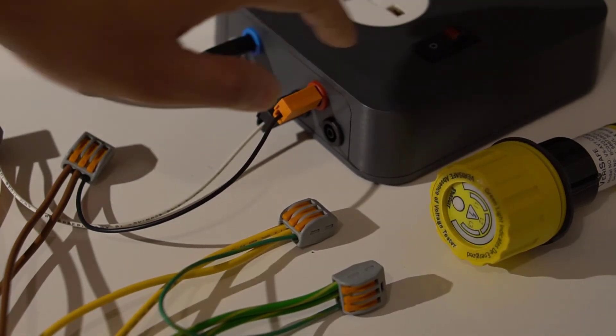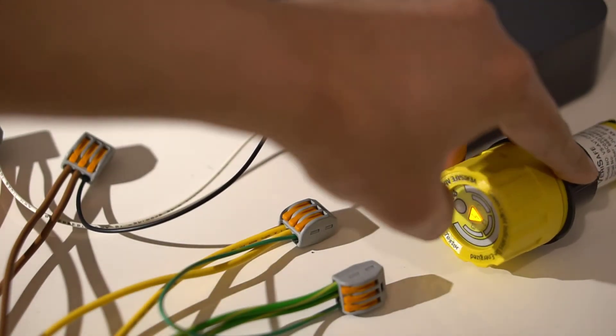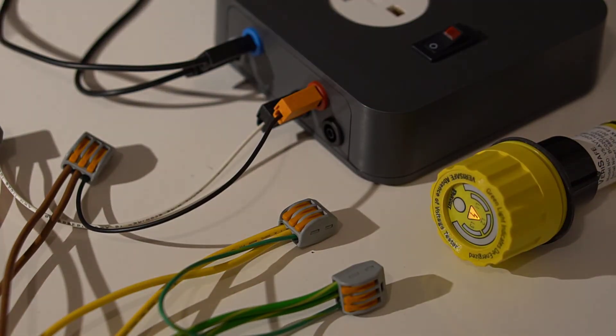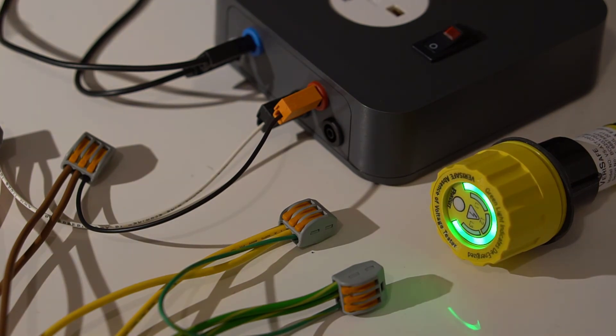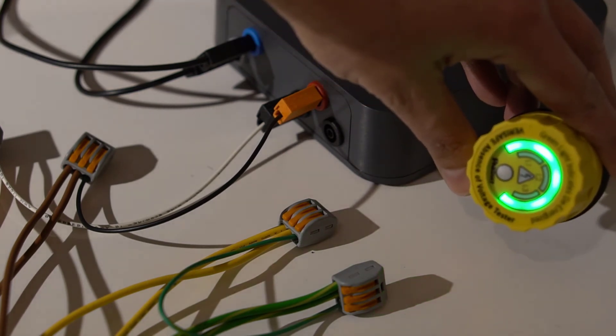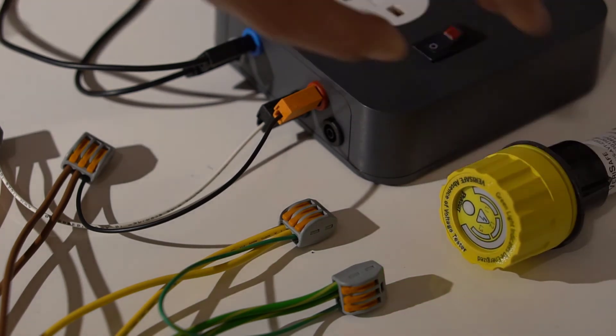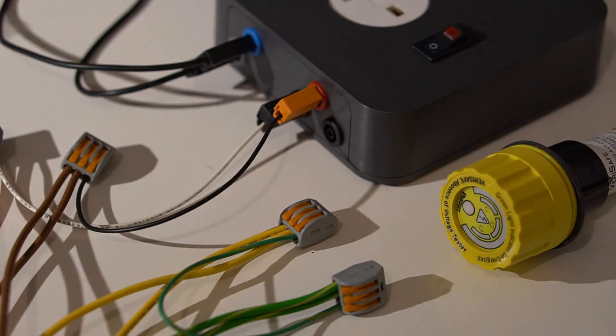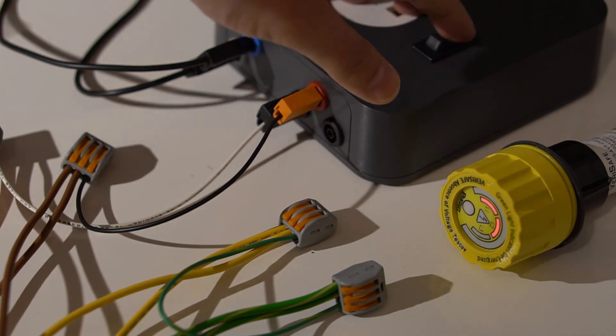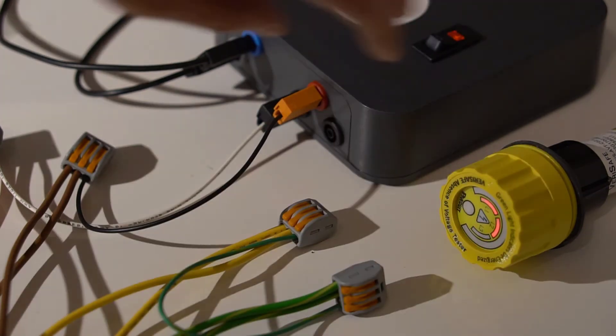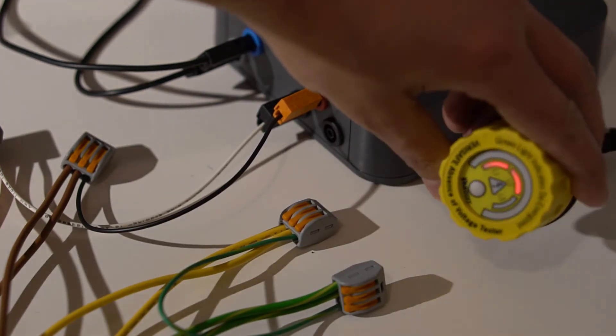At the moment the power is switched off, so if I press the test button I correctly see that the green indication comes up, which shows that the system is safe. Now if I turn the power on, there are hazardous voltages present, and the red indicators come on.